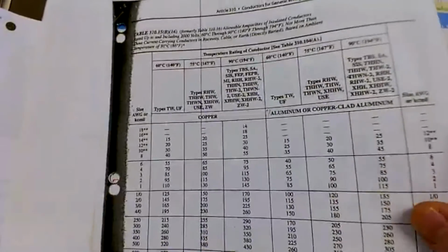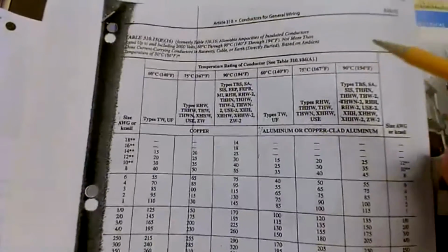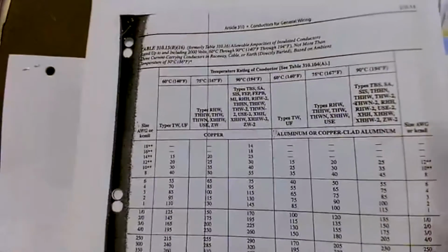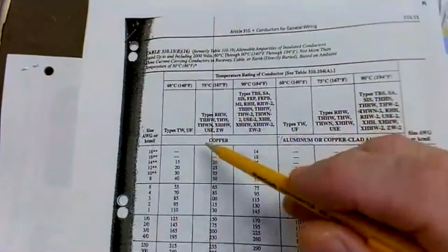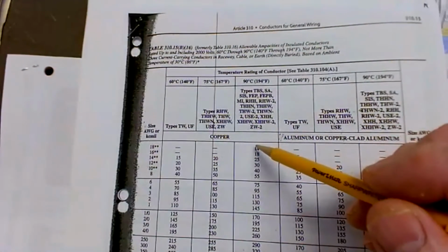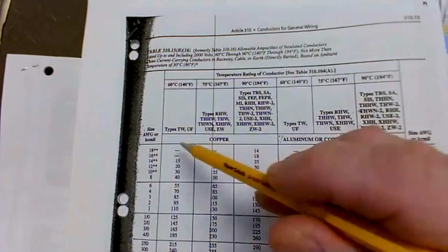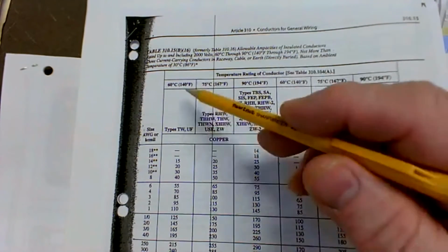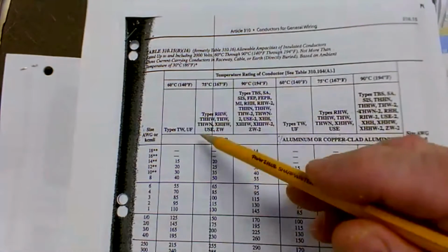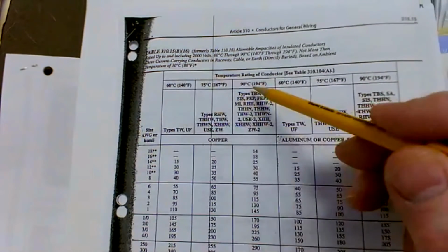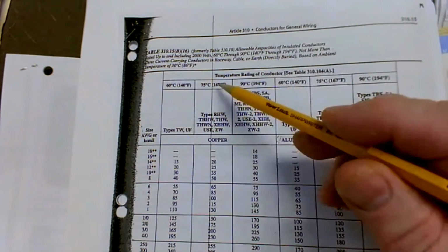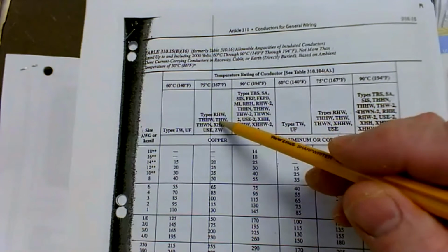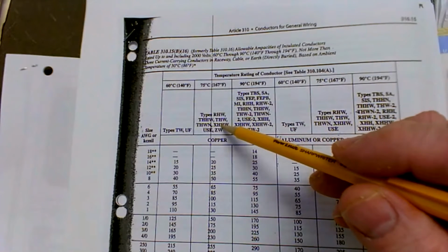So the wire chart that I gave y'all, which is right here, when you take a look at the section that says copper, those first 3 rows are showing copper wire rated at certain temperatures, and then under the temperature ratings there are letters that represent the insulation type that's actually around the wire.